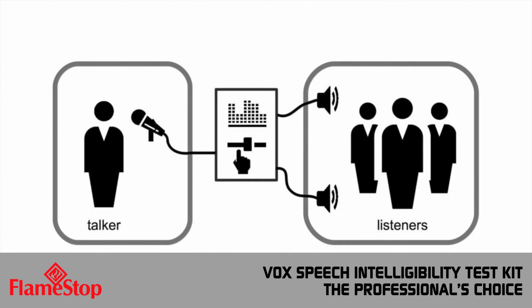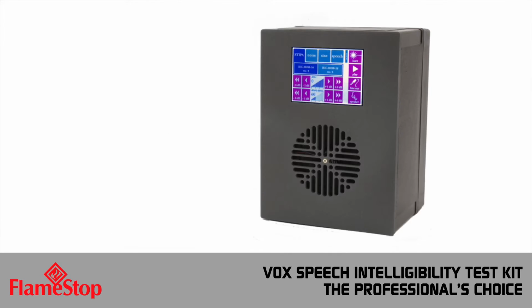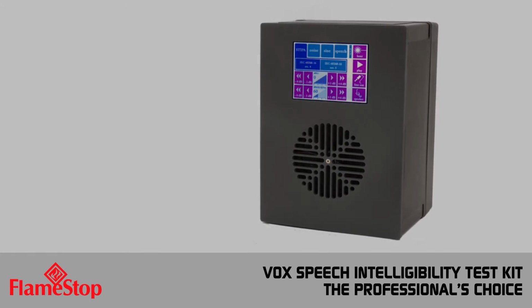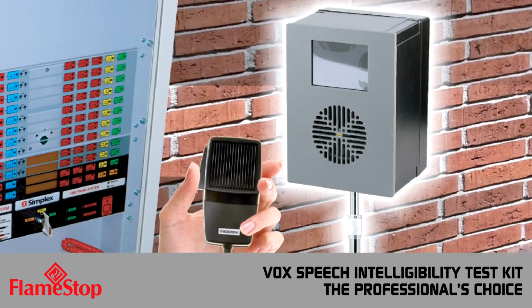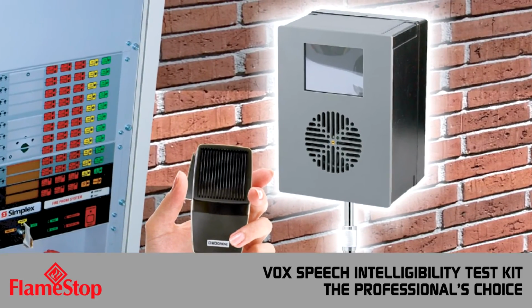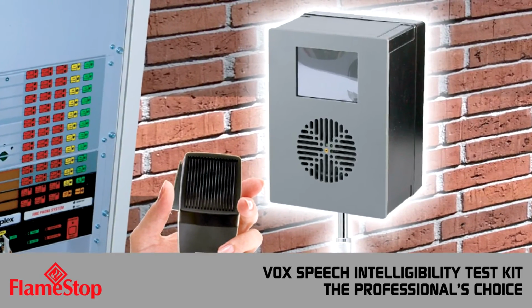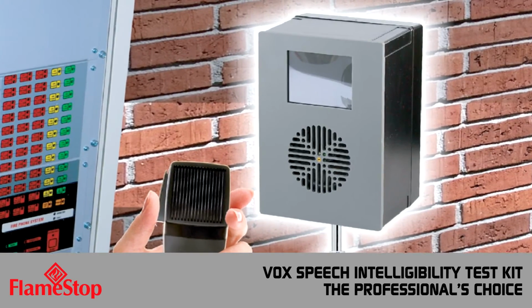In most scenarios, the speech playback through evacuation systems comes from a live talker. In those cases, the STIPA signal from the flash drive cannot simply be uploaded to the sound system. This is when the VOX box comes in very handy. Use the sound system's microphone as you normally would with a live talker. However, instead of a live human talker, place the VOX box in front of the microphone.